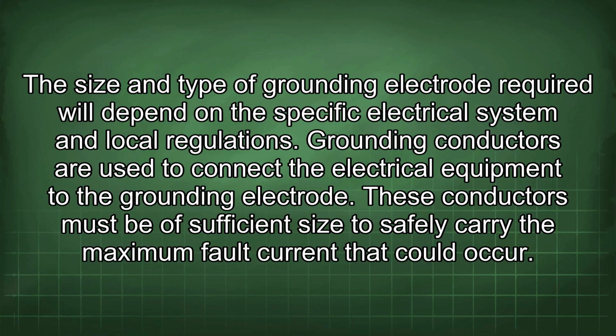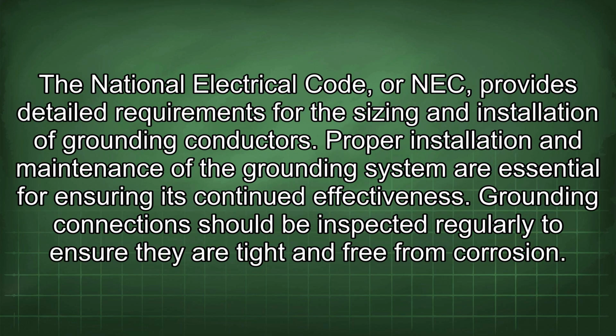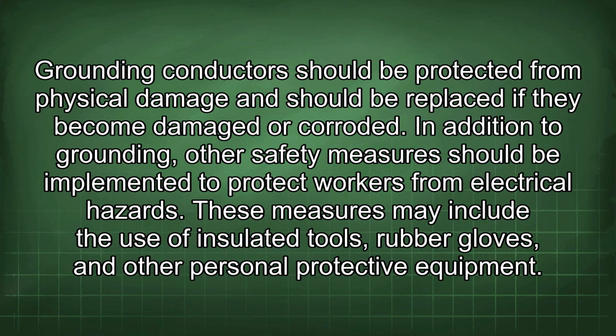These conductors must be of sufficient size to safely carry the maximum fault current that could occur. The National Electrical Code, or NEC, provides detailed requirements for the sizing and installation of grounding conductors. Proper installation and maintenance of the grounding system are essential for ensuring its continued effectiveness. Grounding connections should be inspected regularly to ensure they are tight and free from corrosion. Grounding conductors should be protected from physical damage and should be replaced if they become damaged or corroded.